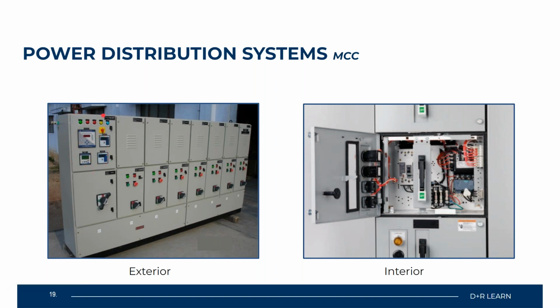So these panels or systems are very important in tracking what's going on with your motor, at the very least at the manual level, meaning that you have a technician on foot providing inspections daily, and they were able to catch that you have an issue with your motor system because they were doing an inspection on the entire MCC. So these MCCs are pretty cool because all of your motor connections are directly here, and you'll be able to isolate your motor system here and do any type of work you may need to do on it.